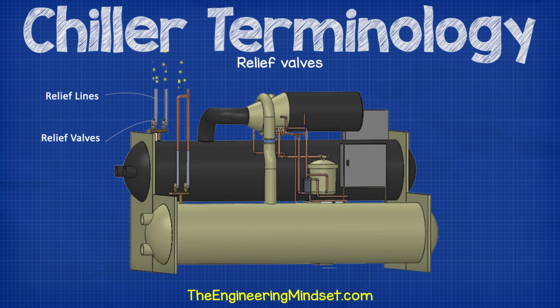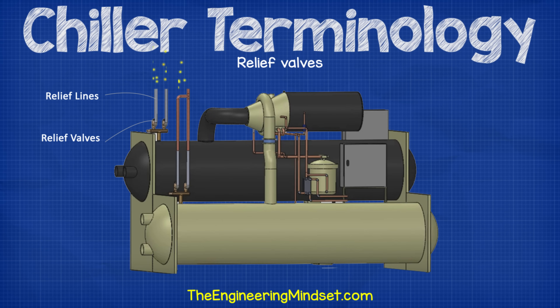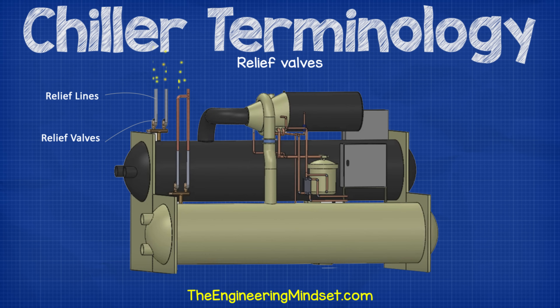Relief valves. Relief valves and lines are fitted to chillers to protect the components and operators from a dangerous amount of pressure buildup within the chiller from the refrigerant. It is rare that this scenario occurs, but it is possible — for instance, in the case of a fire. Typically, the chiller will use a spring-loaded valve which opens automatically if the refrigerant pressure is more than the spring pressure. This will allow the refrigerant to safely vent to atmosphere, and the valve will close again once it reaches a lower pressure.